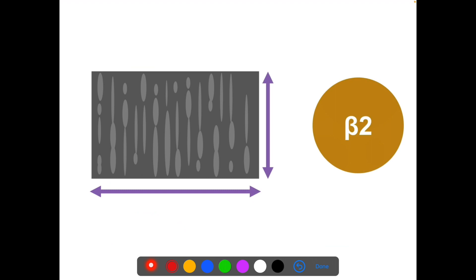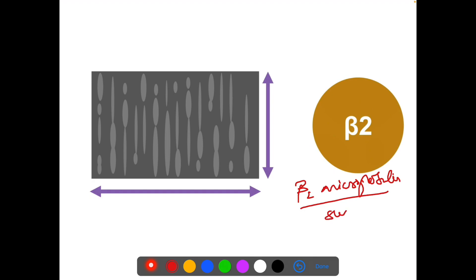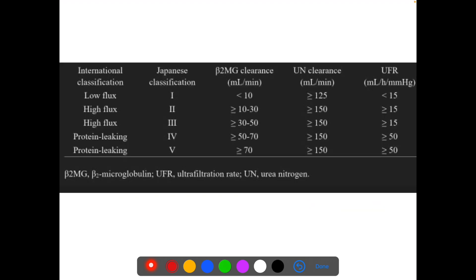How permeable a dialyser is — or how good a dialyser is — can be classified based on beta-2-microglobulin clearance. Beta-2-microglobulin is a surrogate marker to know the quality of the dialyser. Based on this clearance, they are classified as low flux, high flux, and protein leaking. There is also a Japanese classification of types 1 through 5. Low flux has beta-2-microglobulin clearance less than 10 ml per minute, high flux is 10 to 50, and protein leaking is 50 to 70 ml per minute.